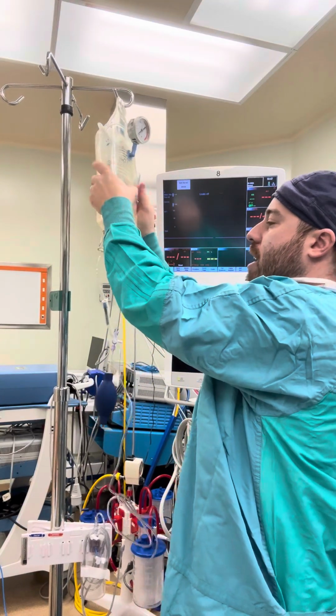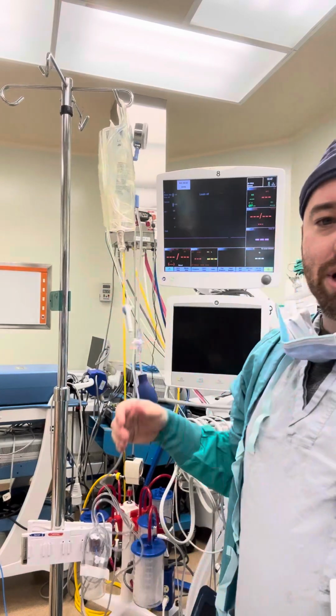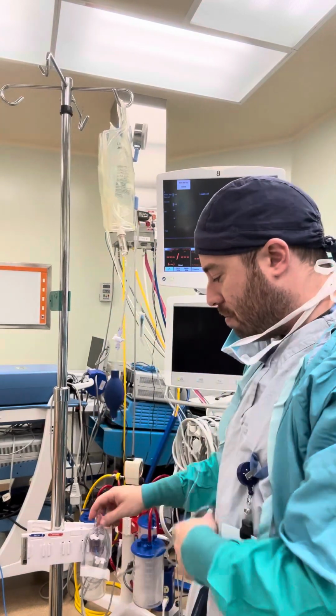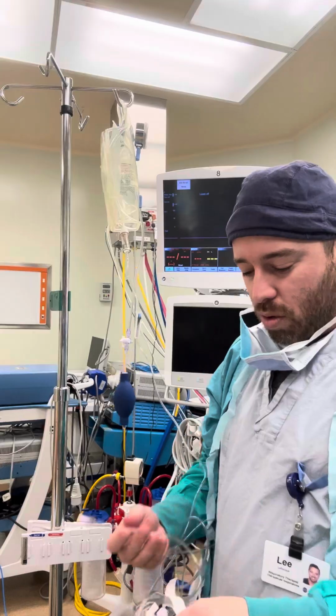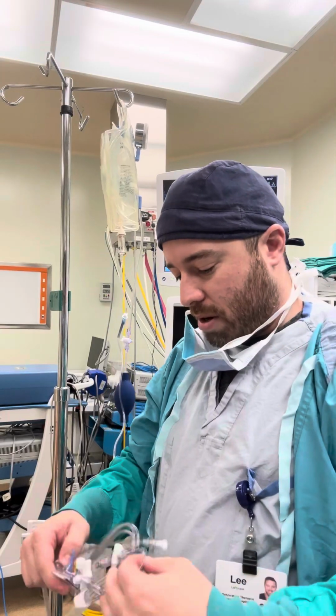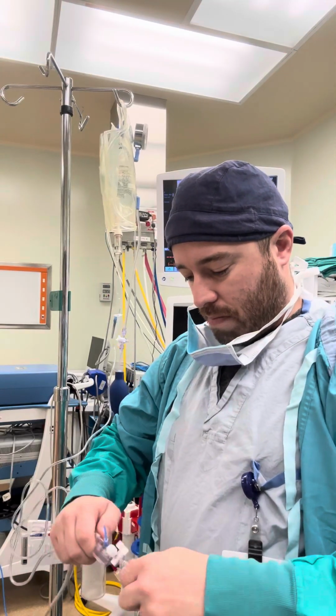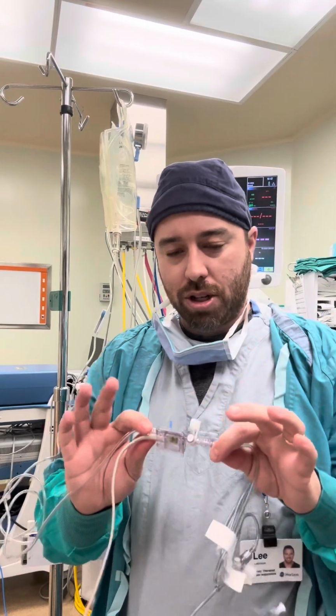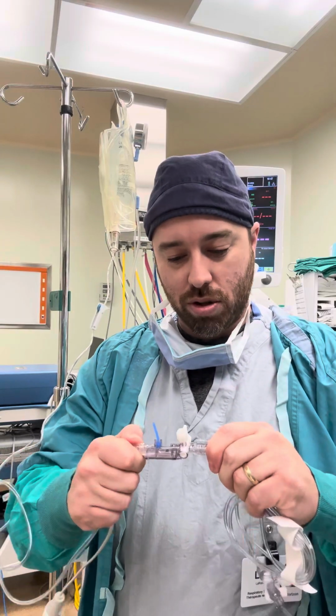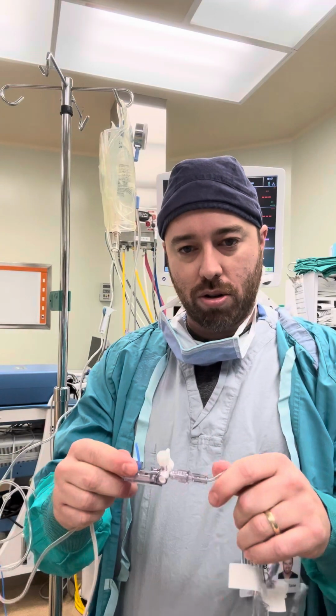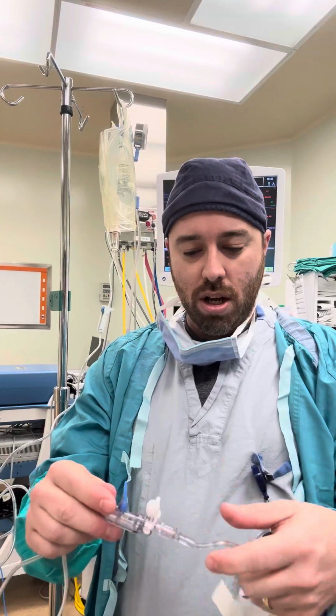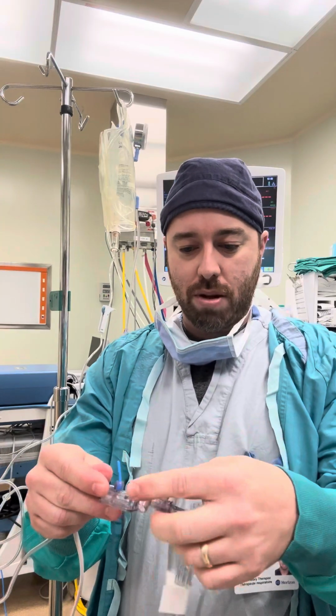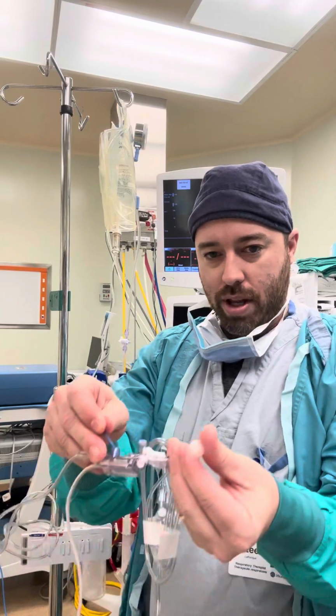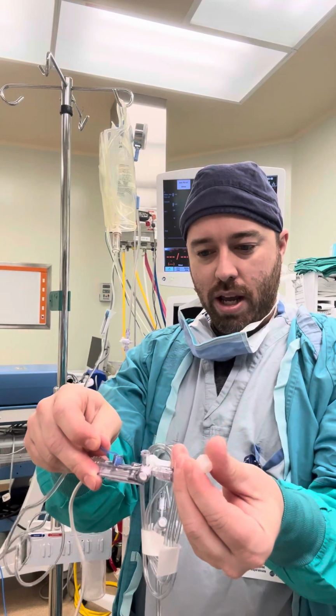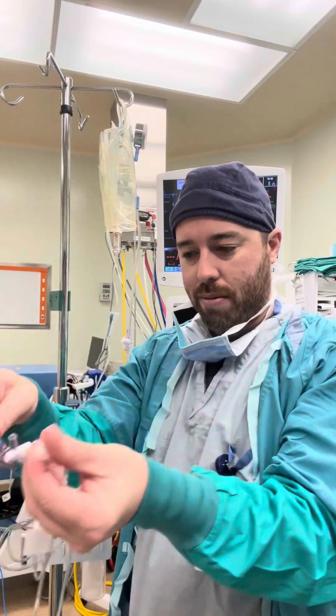I have found generally that it's better to be done under gravity. There's less chance for micro bubbles and the like to develop, so I generally do it that way. The next thing I want to do is make sure that my connections are all nice and tight. So double checking to make sure that those are all correct and in tight position. What I want to do is leave it off to the patient. I slightly open my free air cap, and what I'm going to do is pull on my drain, and then what I want to see is that fluid come and rise up.